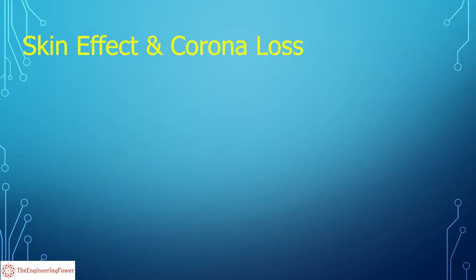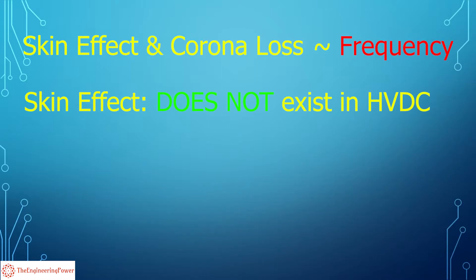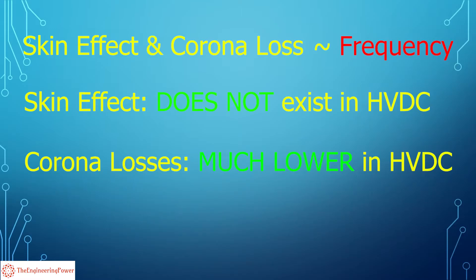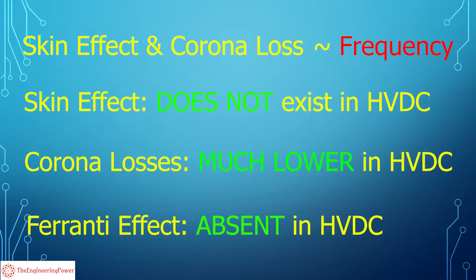Skin effect and corona losses depend on frequency. These losses exist in HVAC systems. Skin effect does not exist in HVDC system, and corona losses in HVDC system are considerably lower as compared to HVAC. Also, the ferranti effect is absent in HVDC systems.